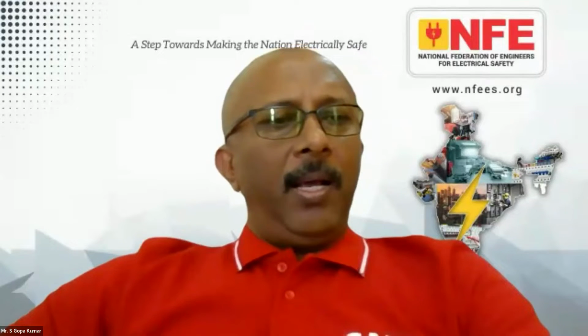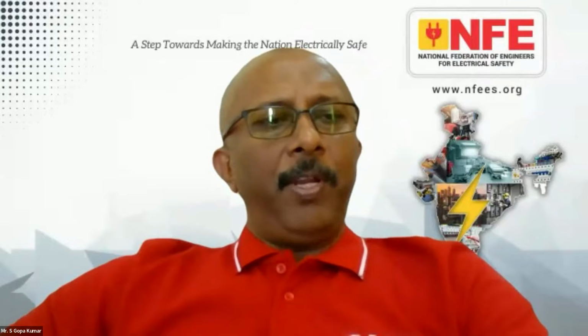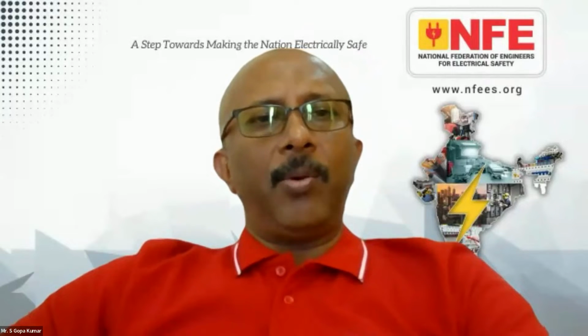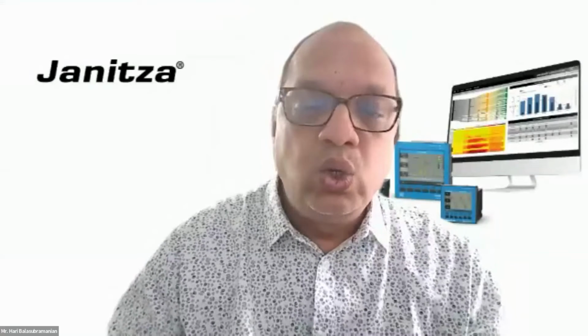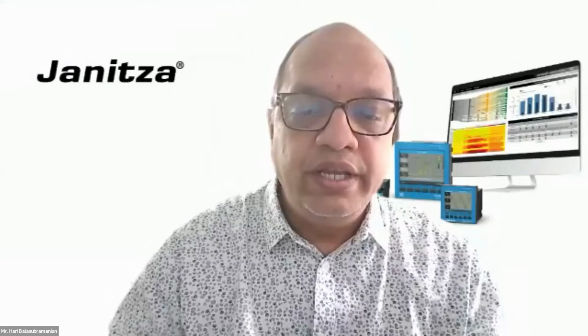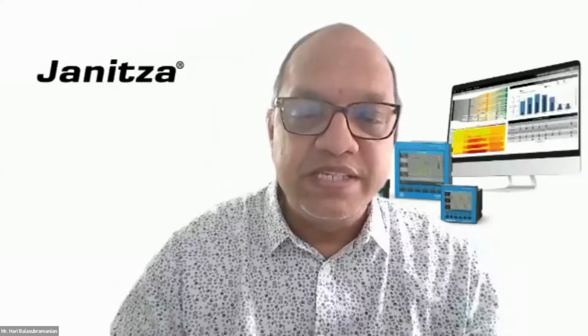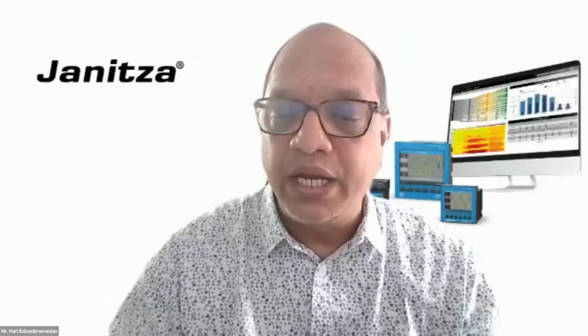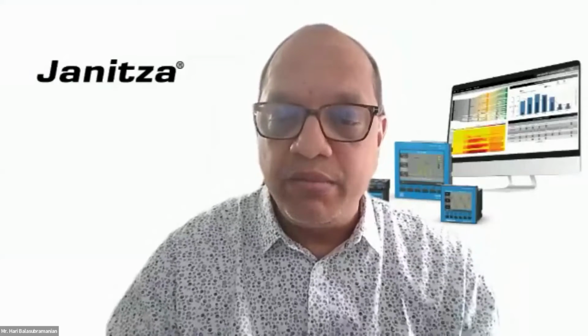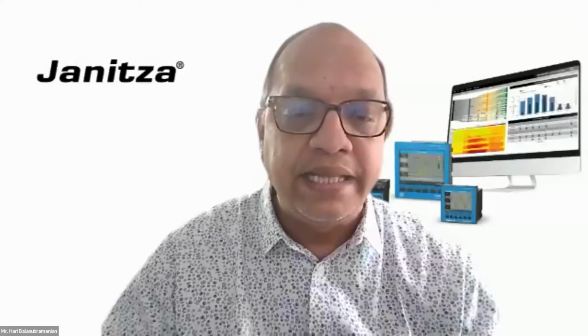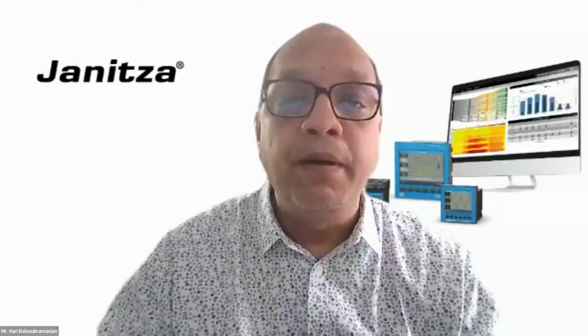Haribala. Mr. Hari, what is the difference between THD, total harmonic distortion, and TDD, total demand distortion? Total demand distortion is the word coined out of IEEE 519. This is specifically for the current. So I would like to explain by sharing my screen for 1 minute so that it would be helpful in understanding that. I will share it.